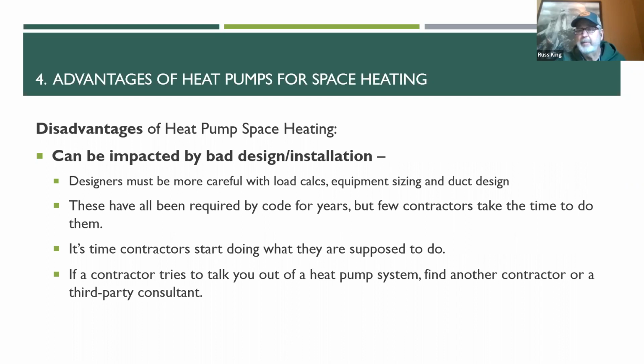They can also be impacted by bad design. I mentioned installed capacity. One of the things that affects installed capacity is how much airflow is passing through the ductwork, where the system is located in terms of temperature and things like that. And so if you don't do a good design on a heat pump, it's likely not to work as well. And so in order for heat pumps to work well, they have to be carefully sized. The capacity has to be carefully determined. The airflow has to be good for it. So you have to have good duct designs and things like that. So designers just have to be more careful in how they design a heat pump system.